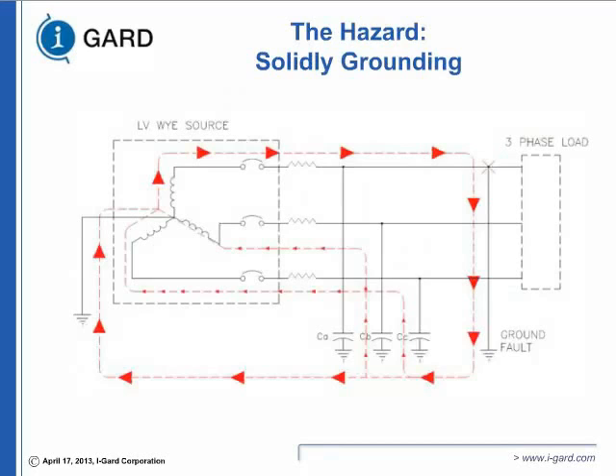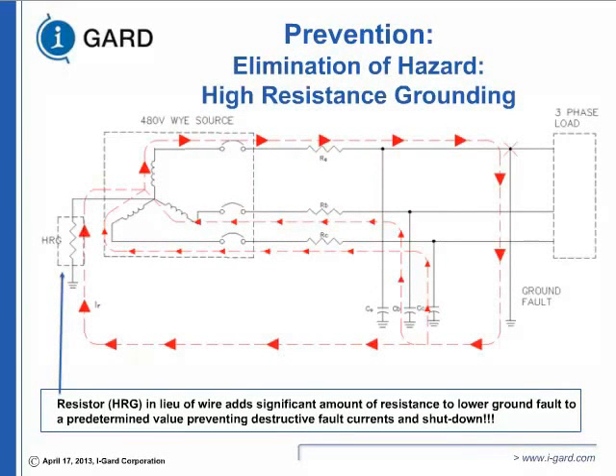This is a schematic you see on your screen. Basic electricity requires that all the fault current has to go back to its source, which is the transformer neutral. And you see some arrows that tell you how it is returning to the source. Now you can see how the protection is achieved. High resistance grounding, what do we do? We insert a known impedance there. Once you insert a known impedance, you're limiting the ground fault to whatever you decide is prudent for your system.